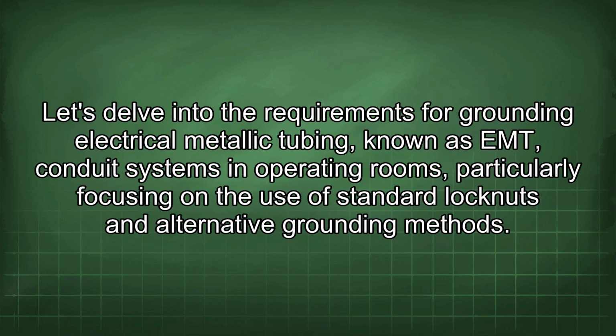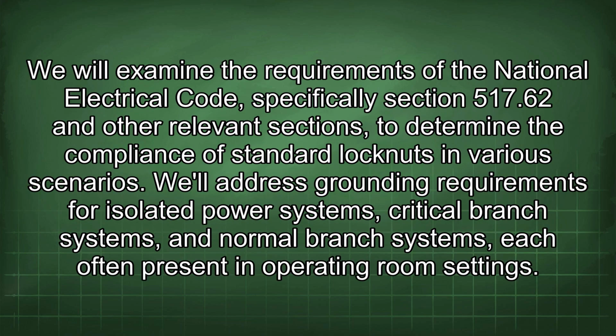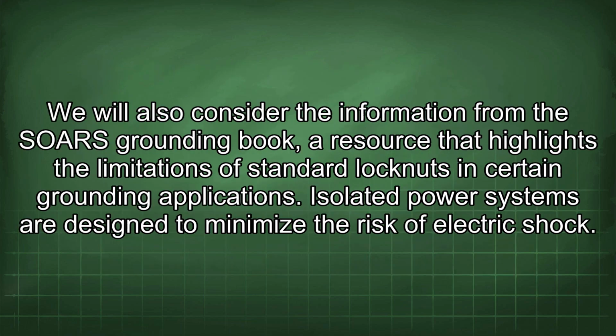Let's delve into the requirements for grounding electrical metallic tubing, known as EMT, conduit systems in operating rooms, particularly focusing on the use of standard locknuts and alternative grounding methods. We will examine the requirements of the National Electrical Code, specifically Section 517.62 and other relevant sections, to determine the compliance of standard locknuts in various scenarios. We'll address grounding requirements for isolated power systems, critical branch systems, and normal branch systems, each often present in operating room settings. We will also consider the information from the SOARS grounding book, a resource that highlights the limitations of standard locknuts in certain grounding applications.